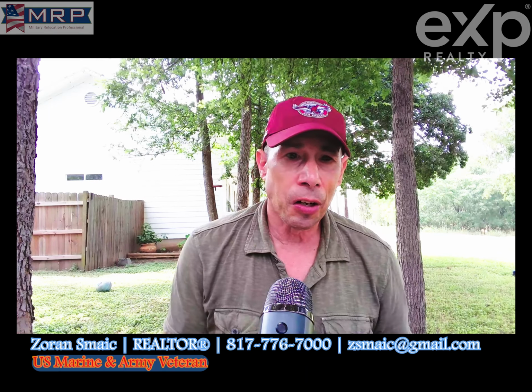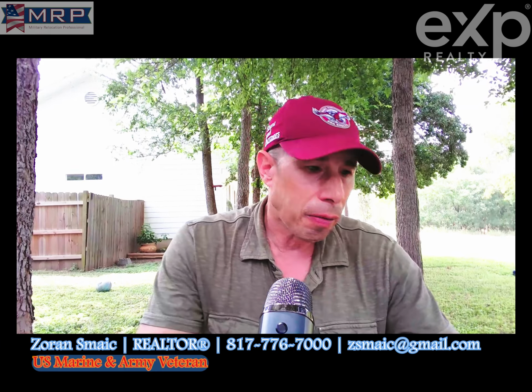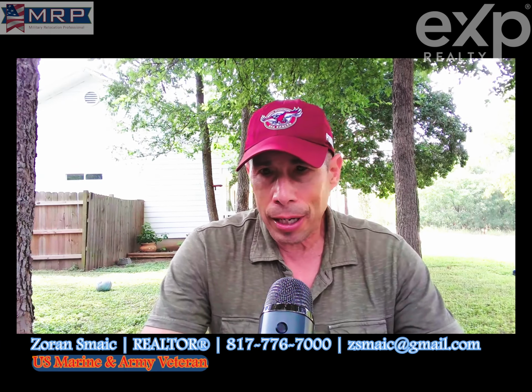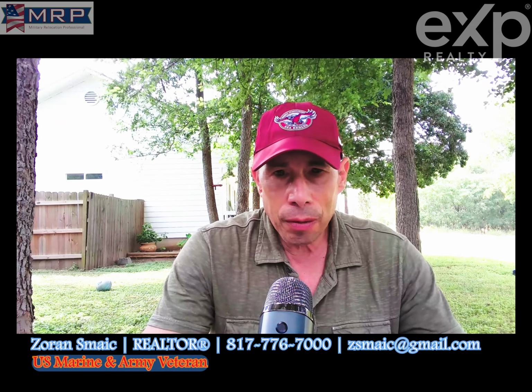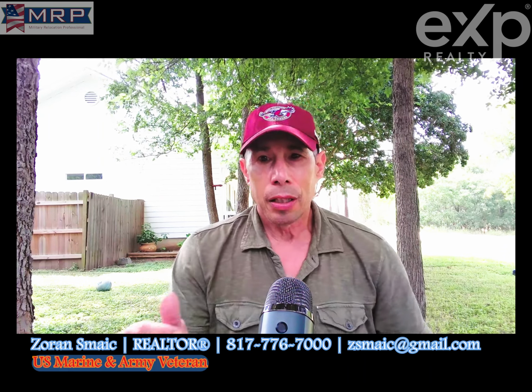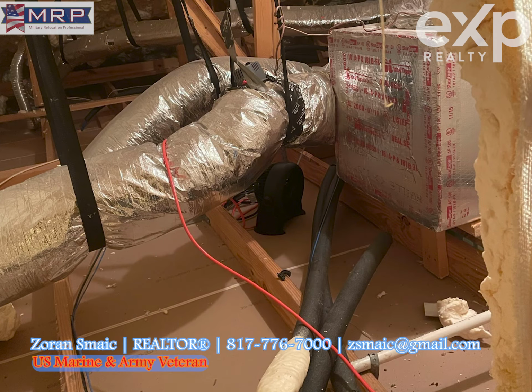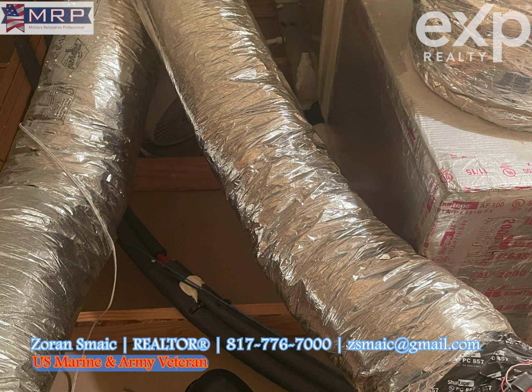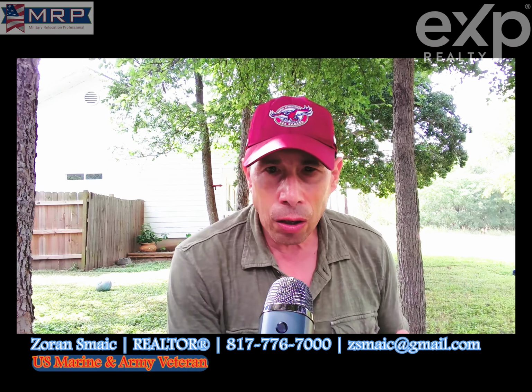The inspector is going to note the location and what type of system is used in the home. He's also going to look at the primary condensate line. That's going to be checked to see if it terminates too close to the house or the foundation, which should be 1.5 feet from the foundation. The inspector will go into the attic and note the service walkway to the HVAC. He's going to see the crawl space to see if you're able to get in close to the HVAC, and see if it's properly installed.